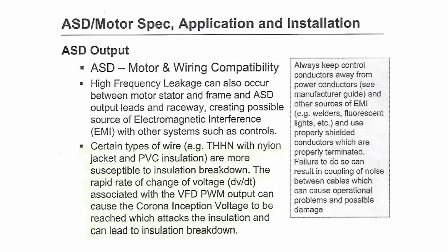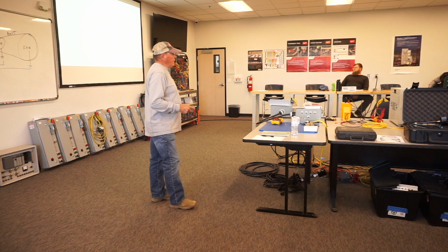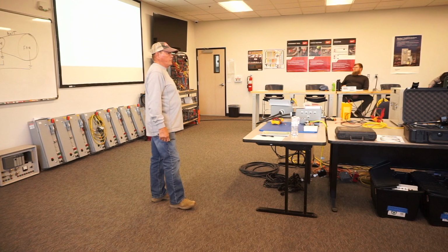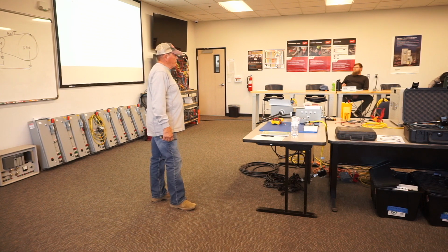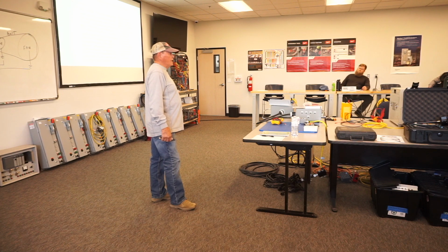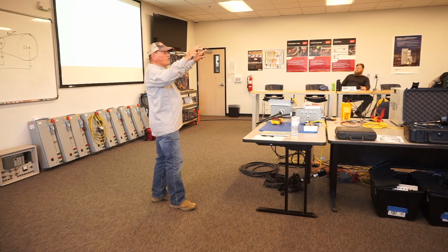And that switch mode power supply puts out RFI and EMI noise that's going to affect anything that's close to it. And if you have an opportunity to drive next to a 900 kW inverter, put your radio station on an AM station and see how close you can get to that inverter before you have to turn your radio off, because of all the EMI and RFI coming off that inverter. Probably 50 feet is about as close as you can get to those inverters. And you have to turn your radio off. So you can only imagine what it must look like if you could see it.